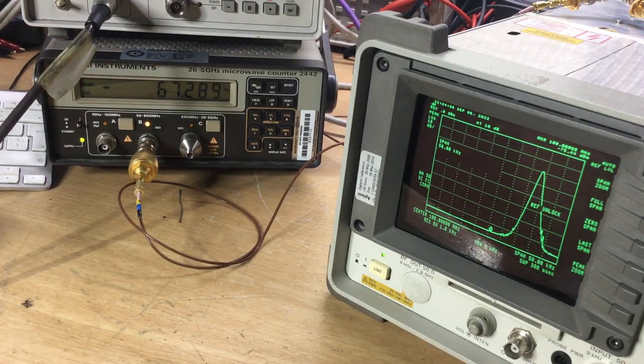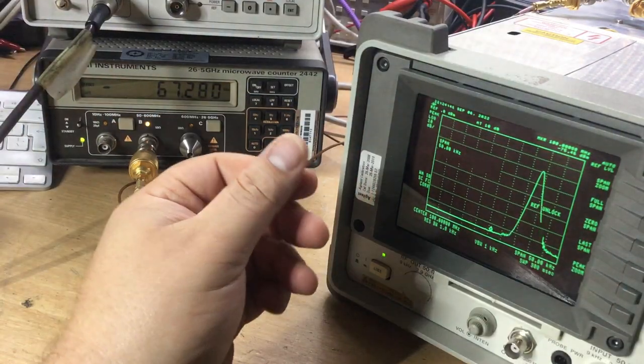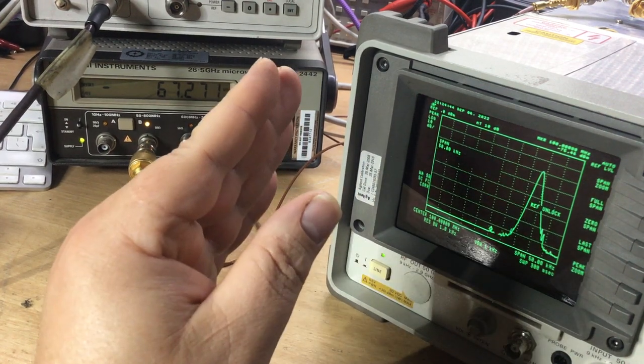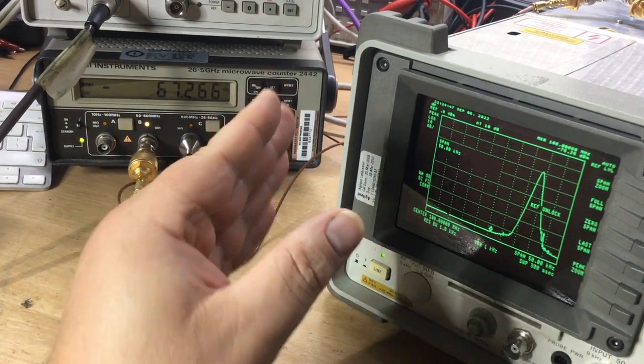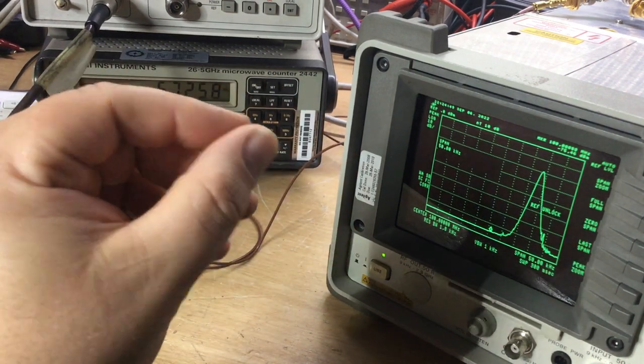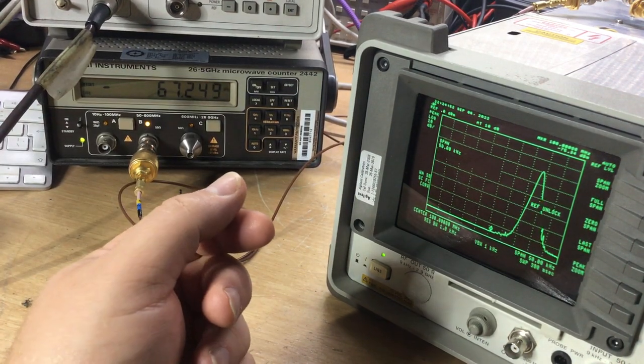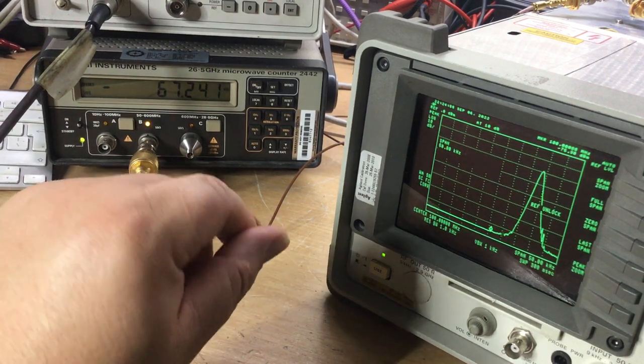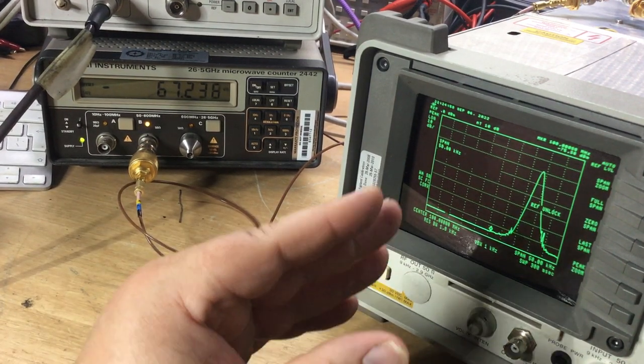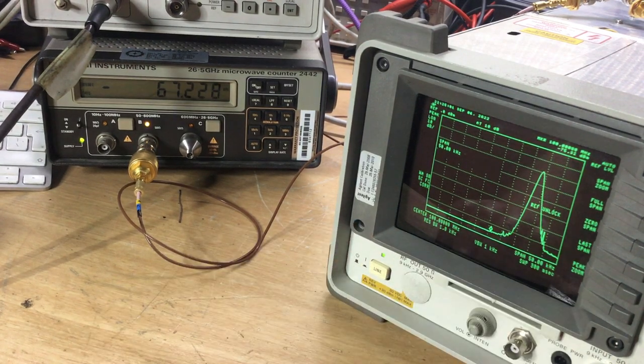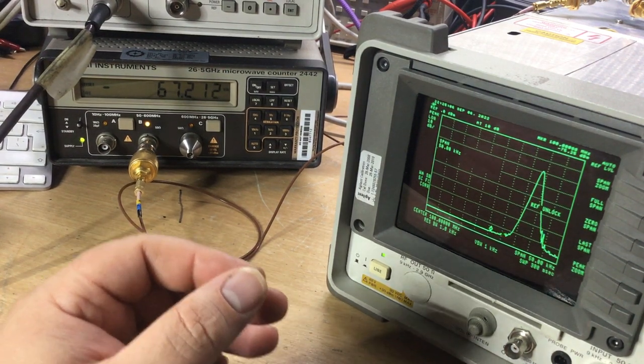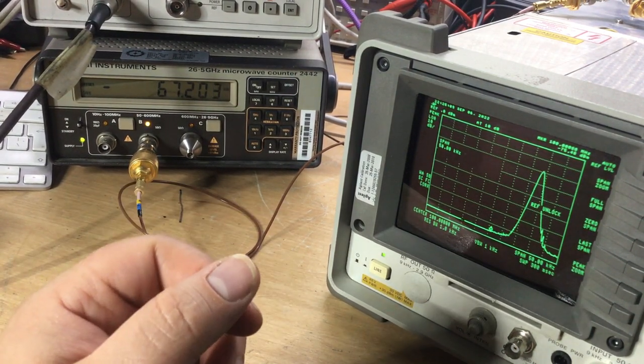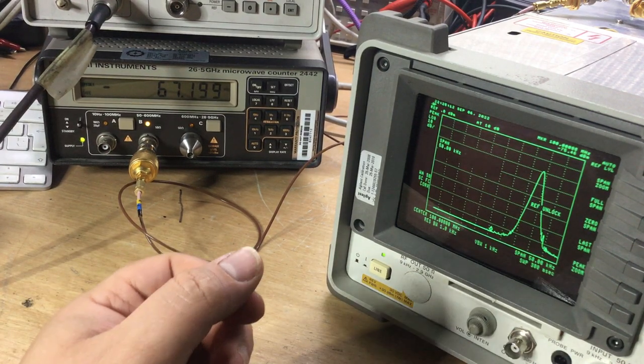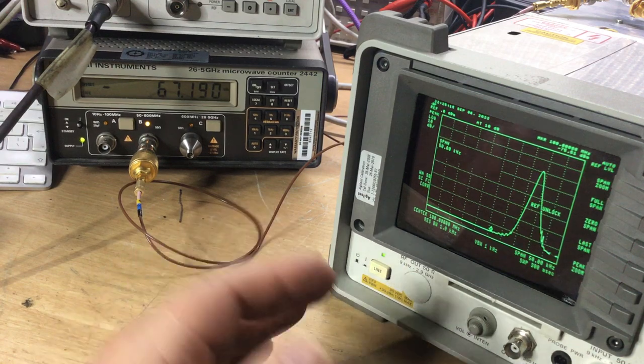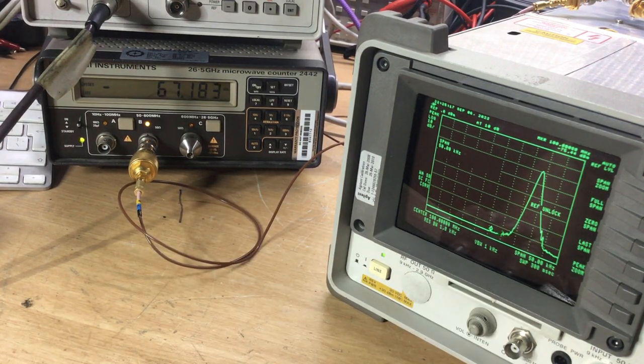Now what I tend to do in that case is I'll adjust the actual potentiometer to midway on the 600 megahertz third converter, the A9 board. So at the moment it's fully counterclockwise, and I'd probably set it midway between counterclockwise and clockwise, and then adjust the coarse frequency adjustment of the 10 megahertz oscillator to try and net that frequency in. Then the potentiometer that's currently on the 600 megahertz converter would then be adjustable either way in order to finish off the final part of the adjustment. So that's something we can experiment with now.